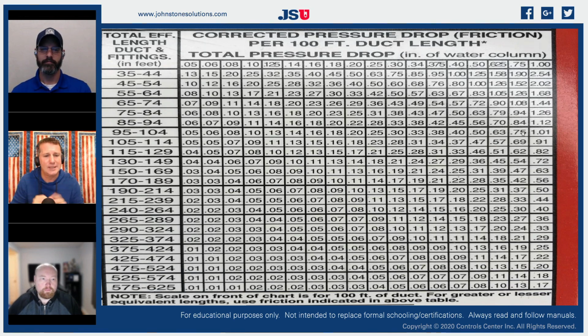because there's two different ways that you can size, and I've always determined that it's either a left brain person or right brain person, whoever's dominant on the left or dominant on the right, whether they start from the plenum and work their way out, or they start at the out and they work their way back. Because I have had both in class and they both come up with the same answer. Some prefer to start at the furnace, some prefer to start at the boot. So we will discuss all that, and we will lay out an entire duct system using a duct calculator.